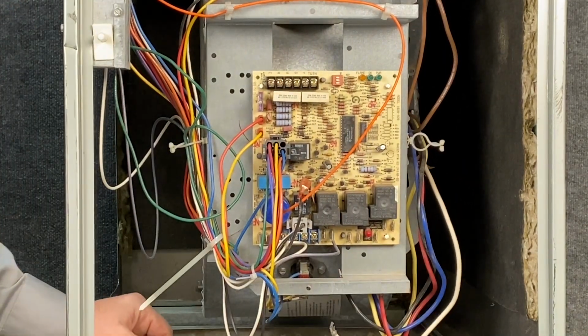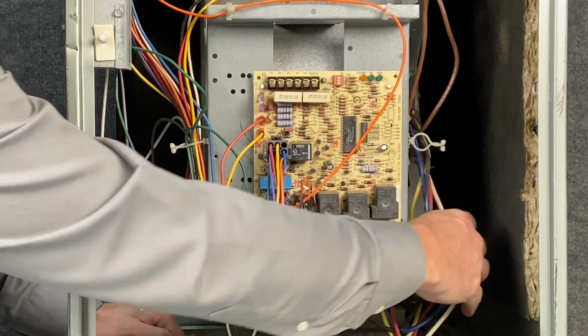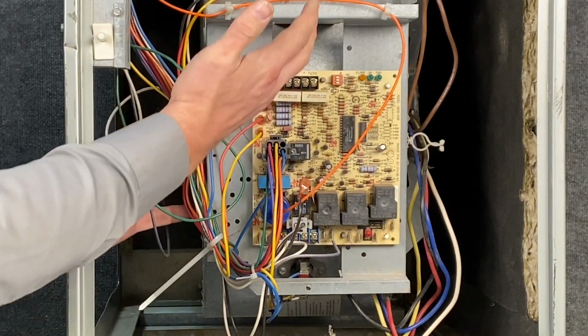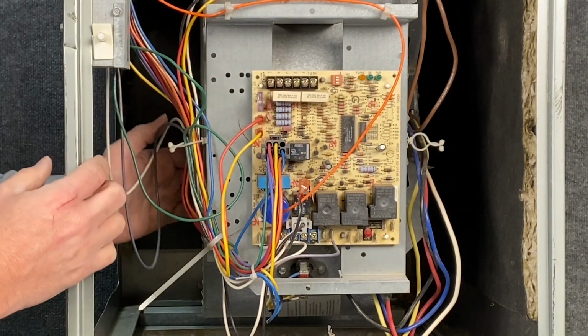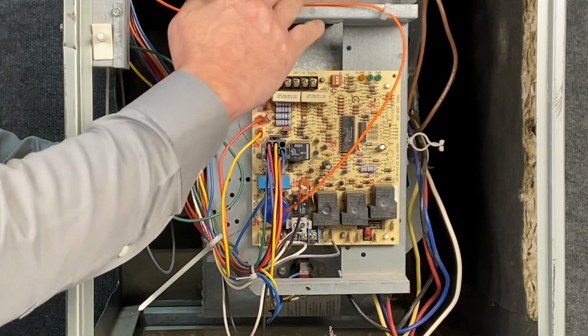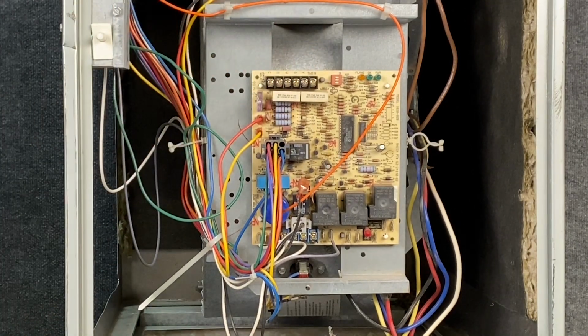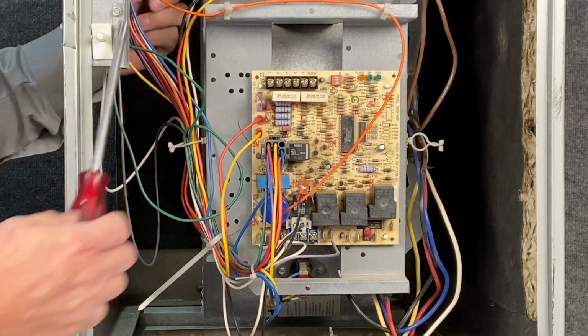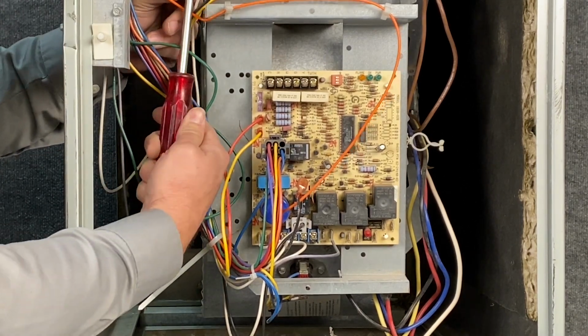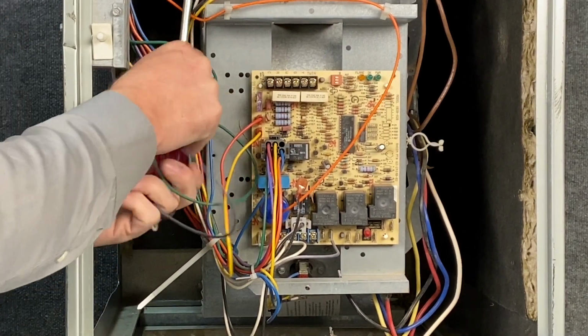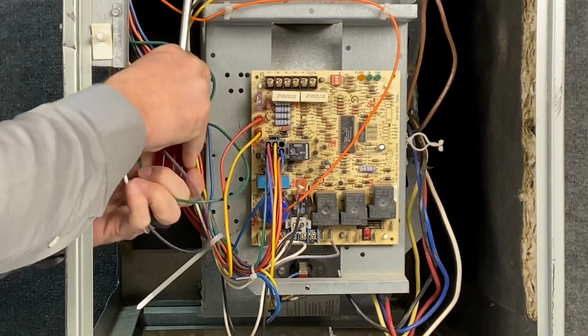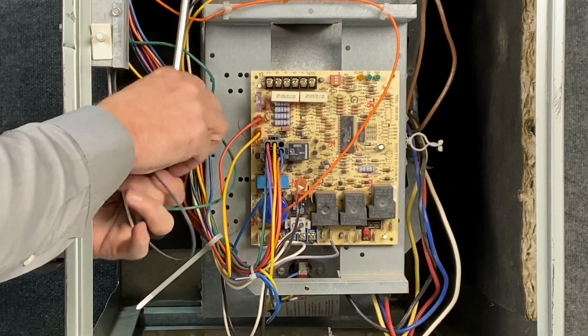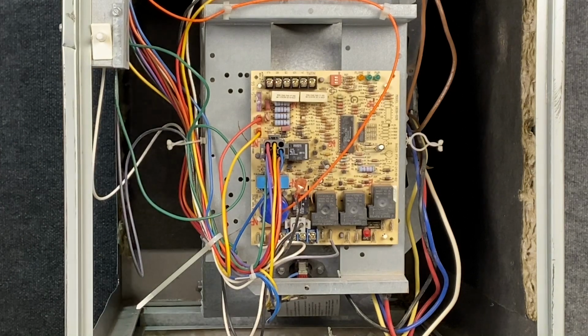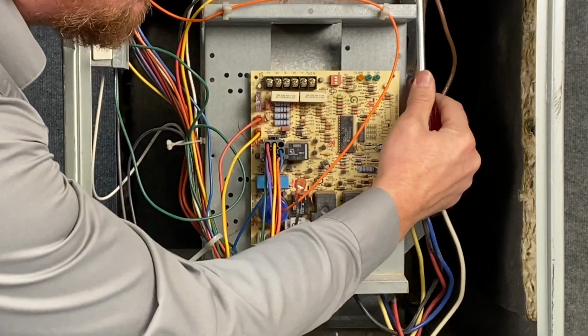So now that we got that off, our wires for our blower are separate. So what we want to do is move these wires out of the way. And on this particular brand, for me to get in there, I need to pull this blower out. So what I'm going to do is undo the two screws that hold the blower housing. So we're going to undo screw number 1. And screw number 2.